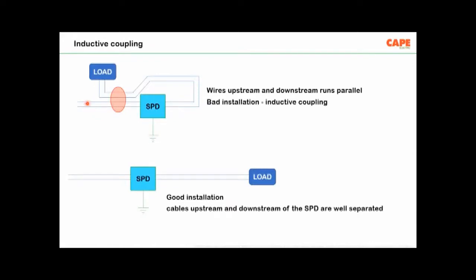Inductive coupling: for example, there is an electrical line and you have an SPD or a filter. The outgoing of the SPD, if the wire runs parallel to the incoming, then of course your equipment will fail. There is no safety which is ensured by the SPD. So the segregation of the circuits, the input circuit and the output circuit, has to be done properly so that unnecessary failures are limited.